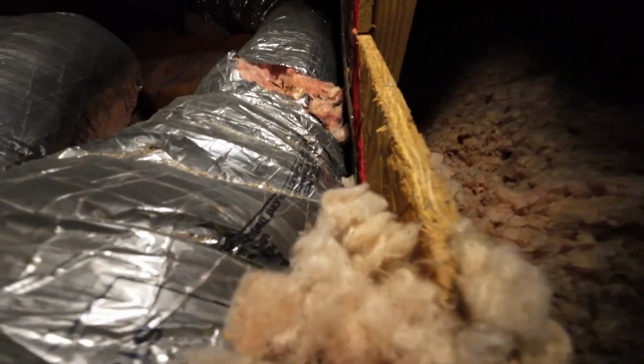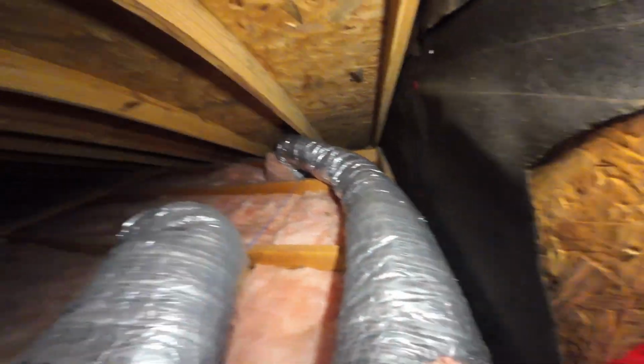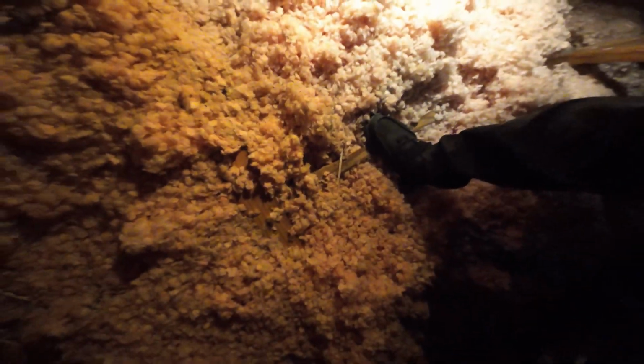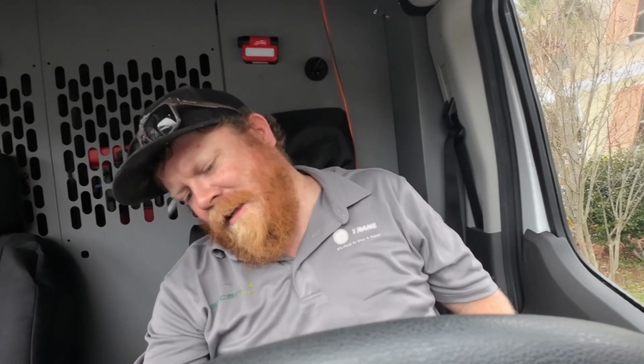We got some exposed ductwork here. Here, I'm going to take this off. Got some exposed ductwork there, pulling in hot air. Insulation could have been a little bit better. Really short, and we only got 4 things coming off, so we'll see. Alright, so I think it is safe to say that unit's oversized. We got 4 6x10 supply vents. The return is big enough, plenty.